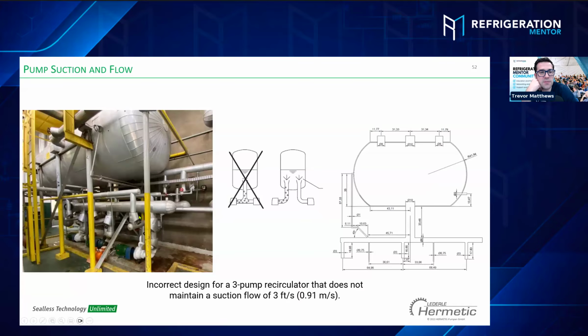Technicians or people who are going to work with the pumps, be careful, because at some point a customer calls me and says, I need to go on site, I have problems with my pumps. I say, okay, before that, send me a picture of your vessel or a diagram. Okay, first of all, the discharge of the vessel is right here, and we have the line all the way here. I don't know the diameter of this pipe. I don't know which velocity. It means we have a problem right here.